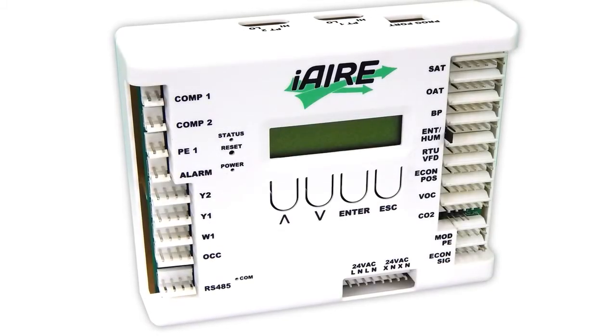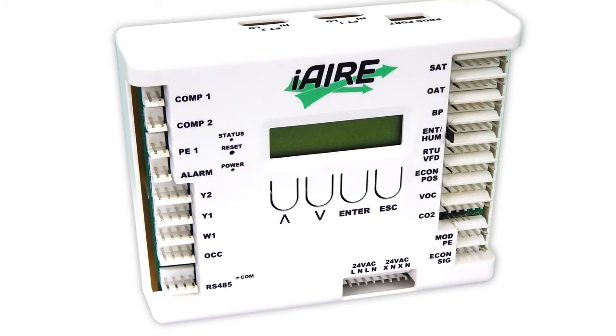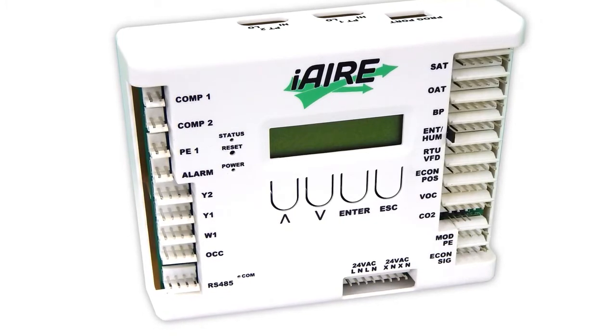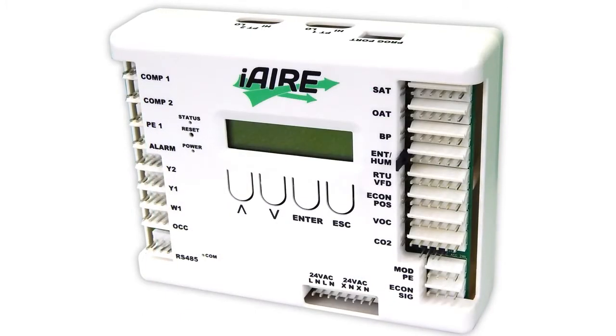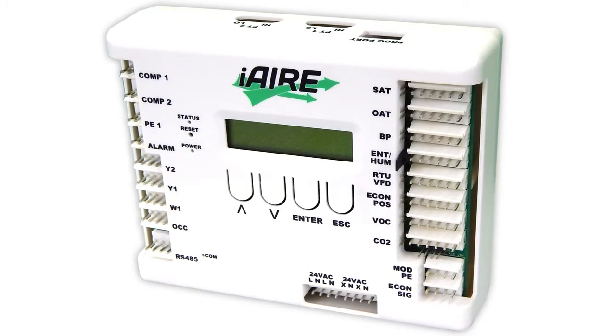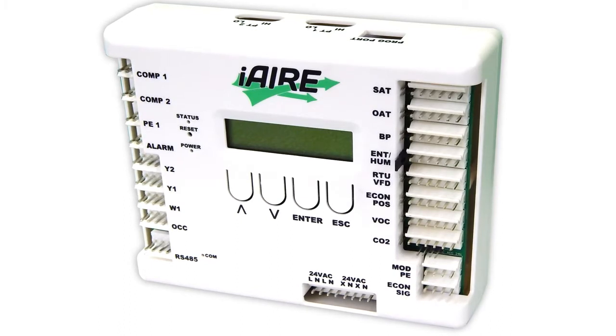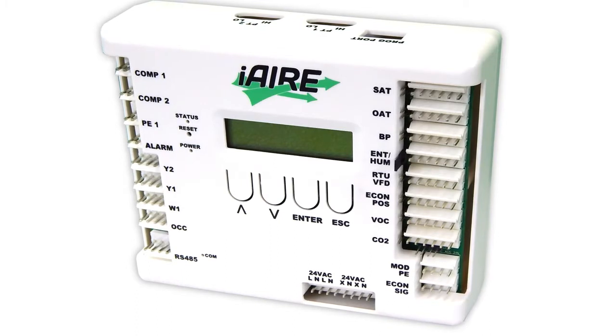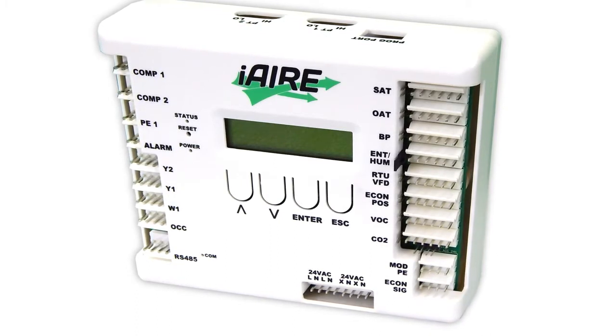The iAire 1000 controller is an integrated economizer and ERV controller. The main user interface on this device is the 2-line by 14-character LCD display and push buttons. The controller doesn't need any external computer or programming to do any of the work or setup. All modes and set points can be modified using the push buttons and LCD.